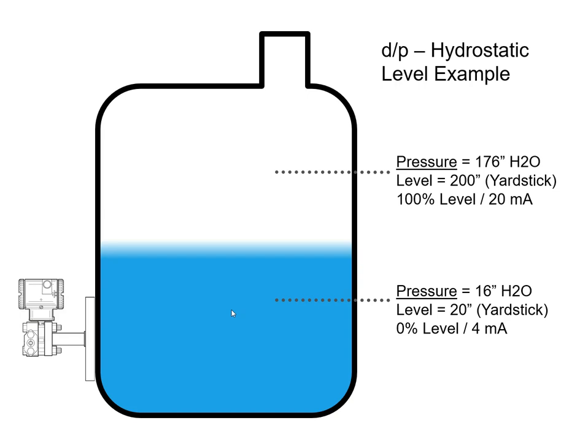But first, to explain buoyancy, I'm going to use DP level or hydrostatic level as an example. DP level remains the most commonly used process liquid level measurement. But this DP cell is actually not measuring level — it's measuring pressure, and we can infer level off of the pressure.